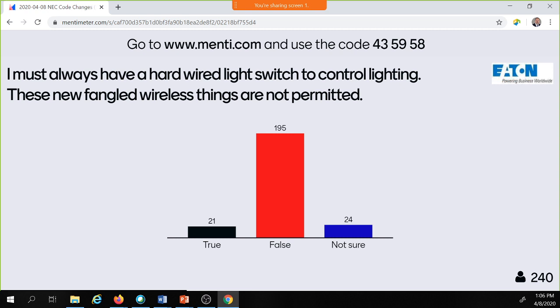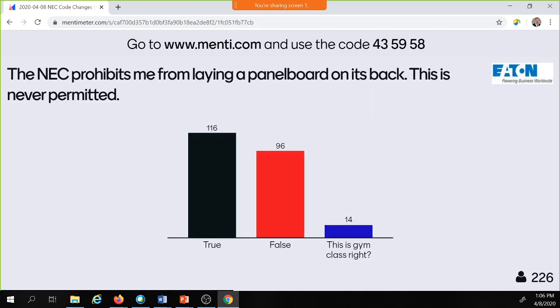So the NEC prohibits me from laying a panel board on its back. This is never permitted. 116 true, 96 false. Well, I would say that if you are on the 2017 code or anything earlier, you are permitted to put that panel board on its back. There's nothing in the code that says you cannot. And that is why the code changed during the 2020 cycle.